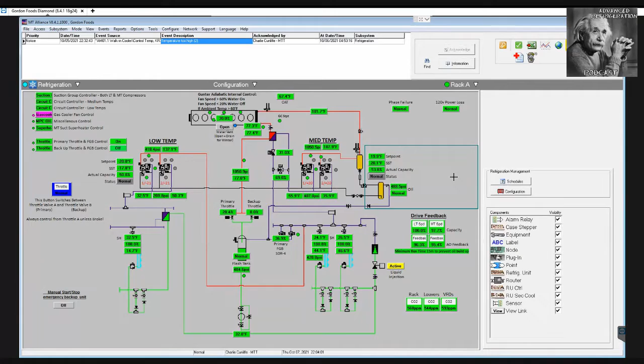I've noticed with CO2 systems, you're doing well if you can get 2, 3, or 4 degrees of subcooling. I've not seen one yet where you can get 8, 10, or 12 degrees. So you've got to be careful with your piping to make sure you've got 100% liquid CO2 getting out to the store. That combination of those two valves by that controller, that's where a lot of the magic happens in a transcritical CO2 system.